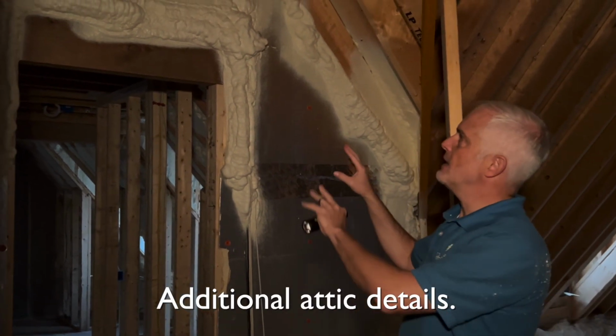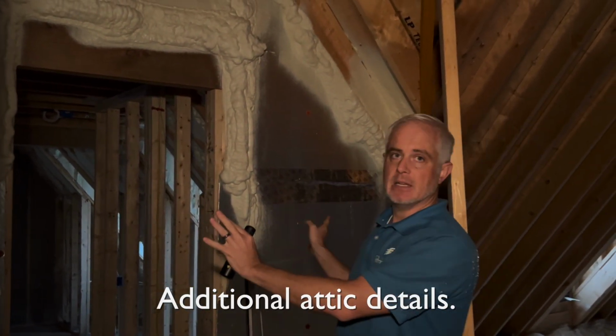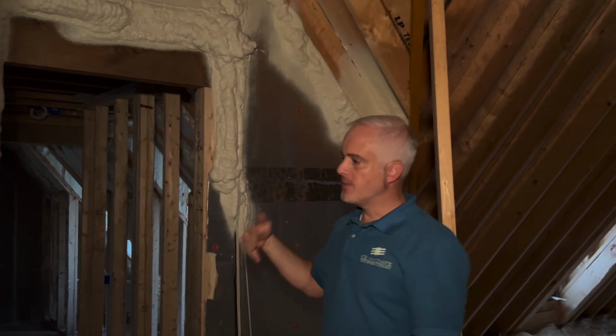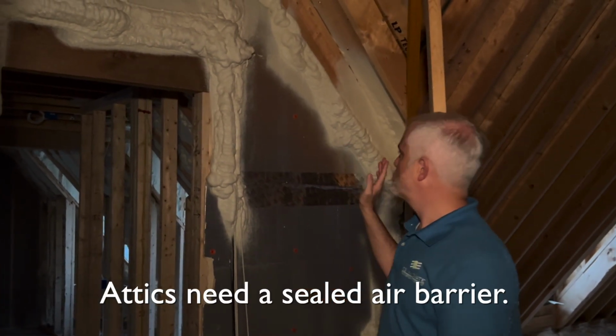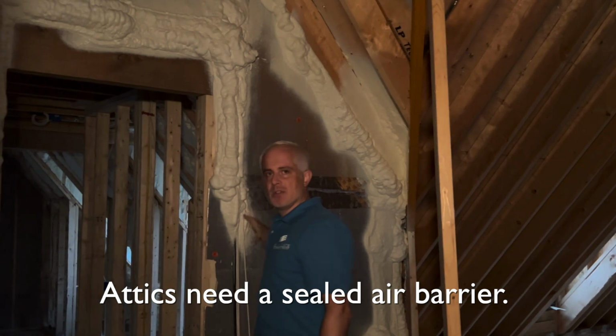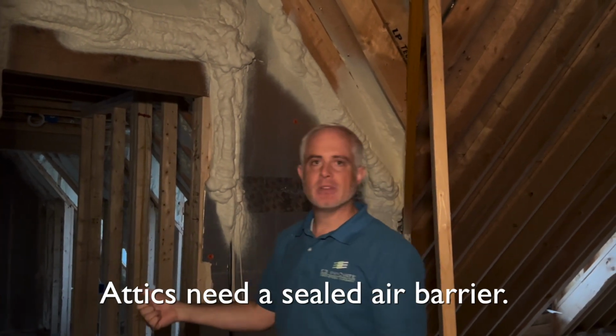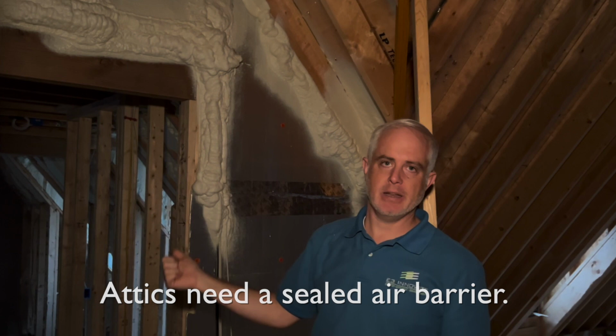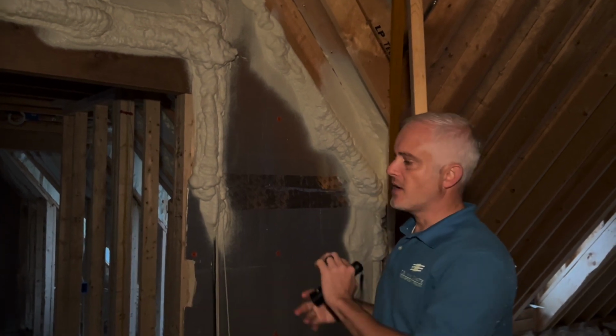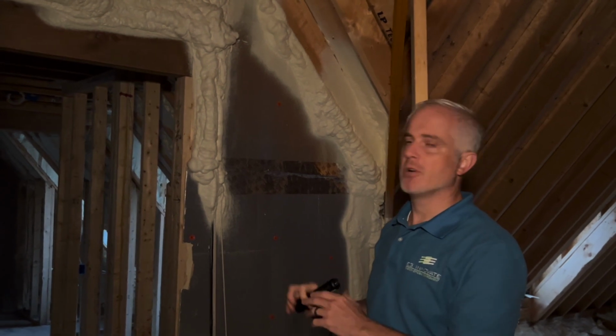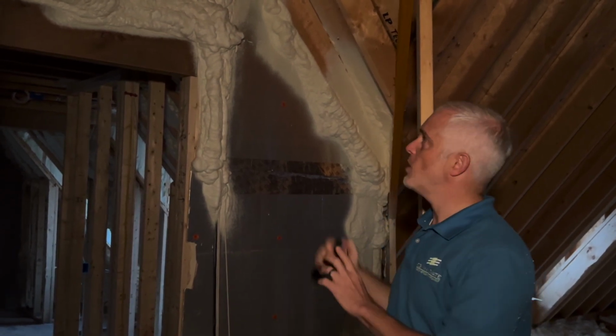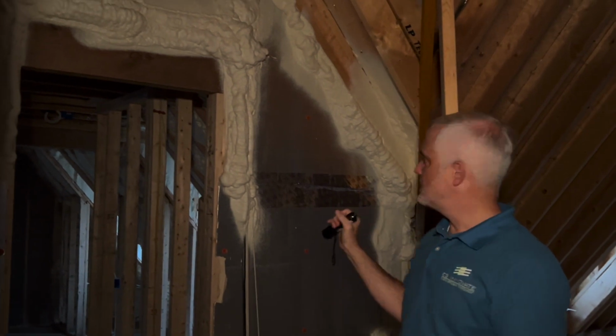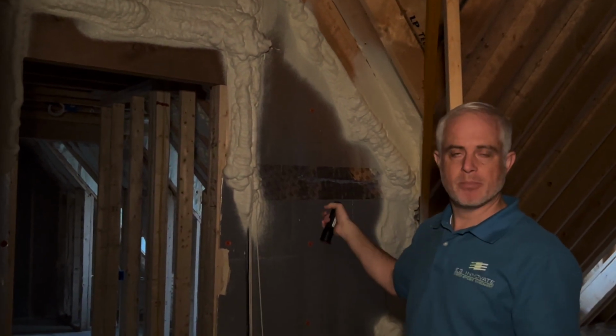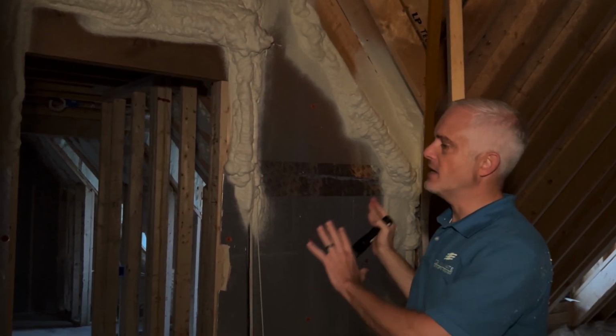So we've stepped outside the bonus room into the attic. I just wanted to highlight the significance of properly sheathing this wall. Oftentimes this detail gets missed. We want to make sure that you provide an air barrier on this wall and that you've properly sealed that air barrier and you've insulated that air barrier. So that's part of the code. It's often missed. Some people just put batts in that wall. They don't perform well, and then people are frustrated by the performance of the bonus room. So this wall needs to be well sealed. This is a foil-faced polyboard that provides a radiant barrier and continuous insulation, and then there's spray foam on the other side.